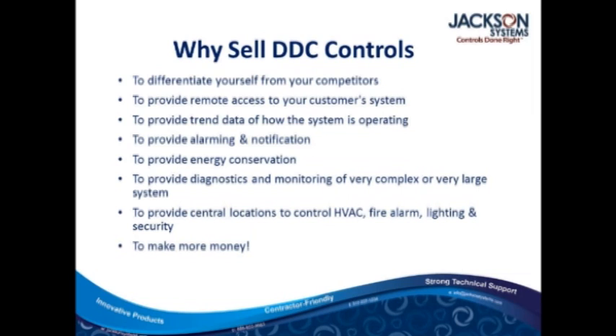If you can provide remote access that ties together with his operation, especially if it's remote buildings, if you have 3 or 4 or 5 or 15 buildings around town, being able to see when those doors are locked in the building is really nice. Being able to provide trend data for your customer. If your customer's always getting complaints that, hey, my room's too hot, elementary schools or high schools, they're the worst. Teachers complaining, I'm always hot, I'm always cold. But if you can provide trend data to show that person who's complaining, hey, company policy or school policy is we're going to keep the building 74 degrees in the summertime, your room's right at it. Here's the documentation to prove that.